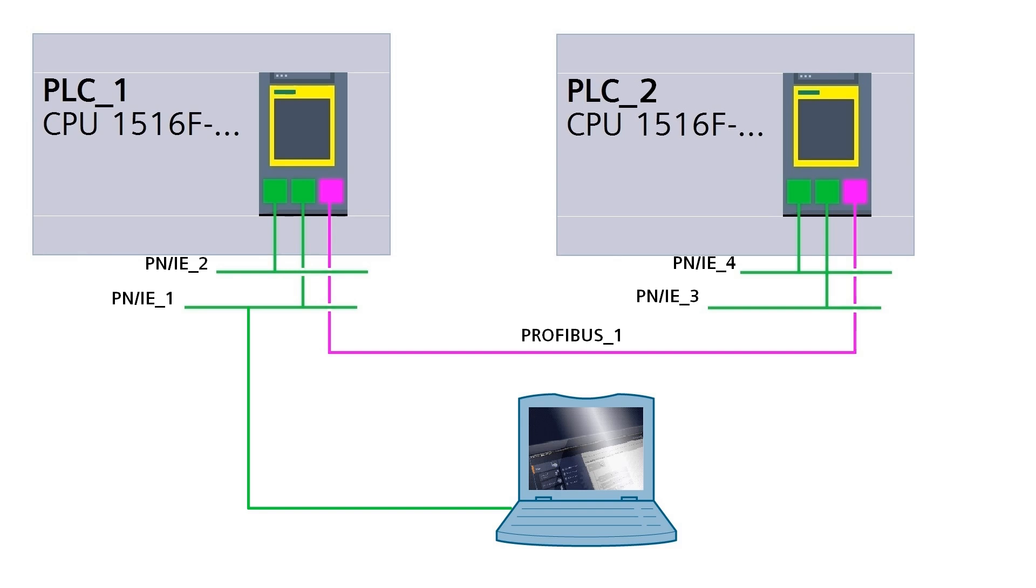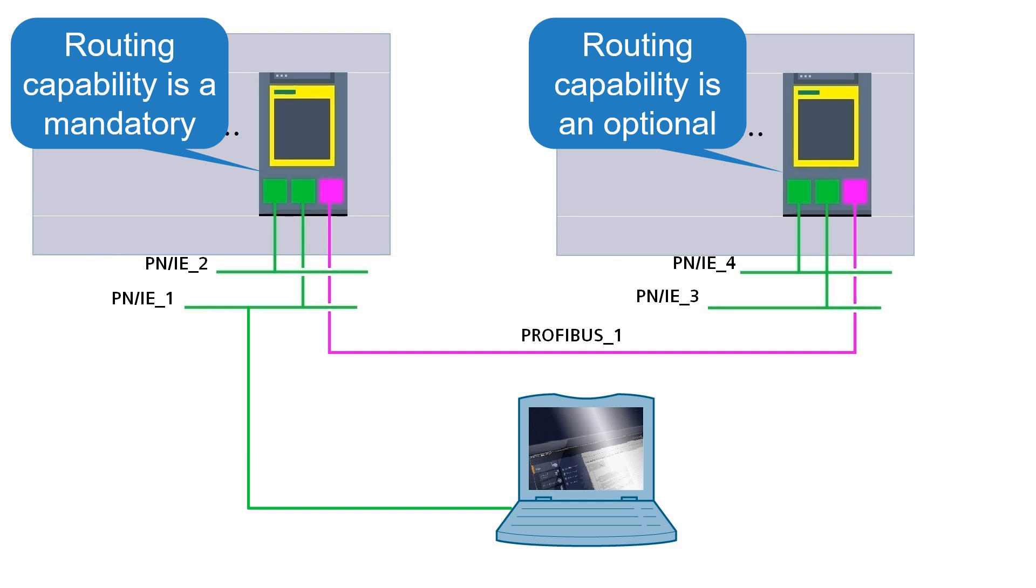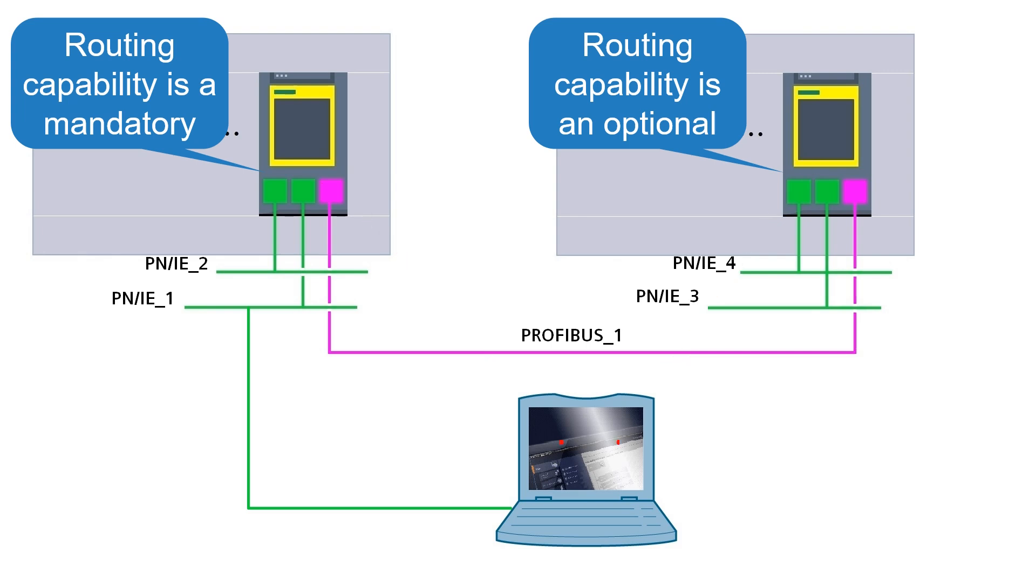To be able to use S7 routing all but last one device must support S7 routing. All the devices must be configured in step 7. As CPUs play the role of an S7 router, the routing information is obtained by downloading hardware configuration to the CPU.